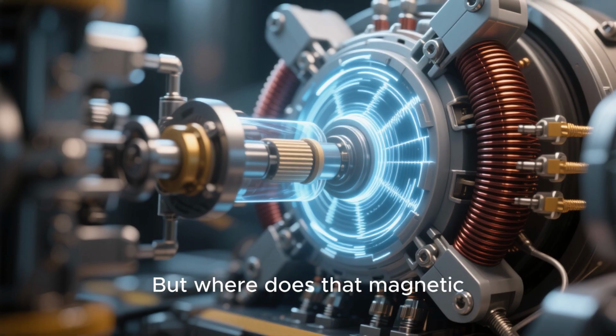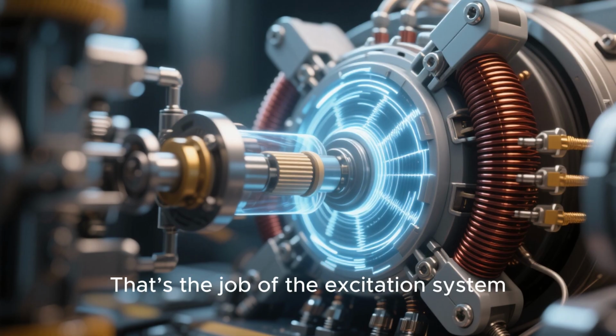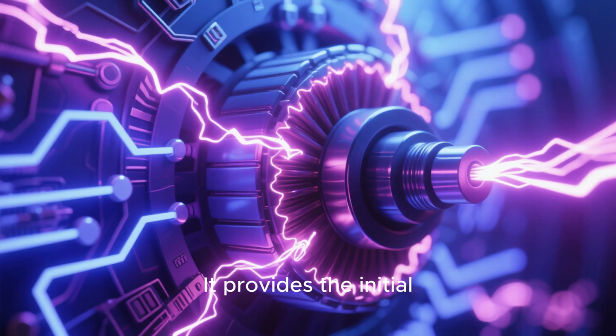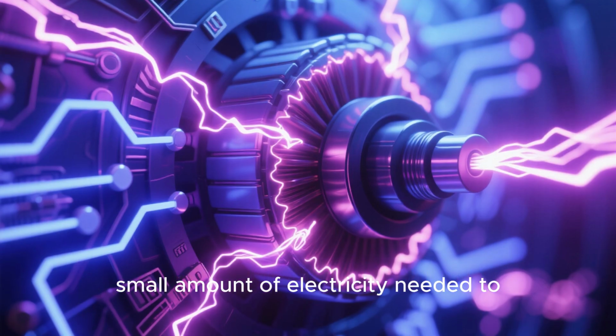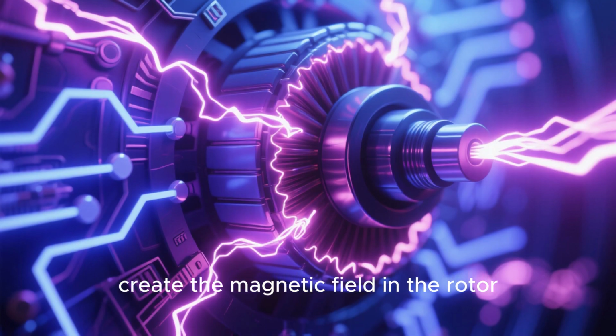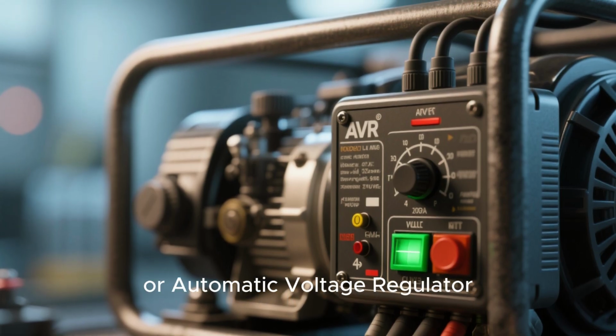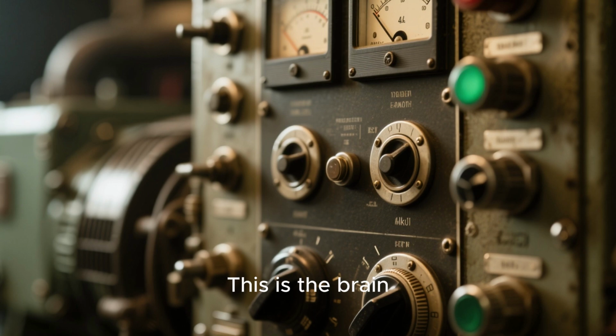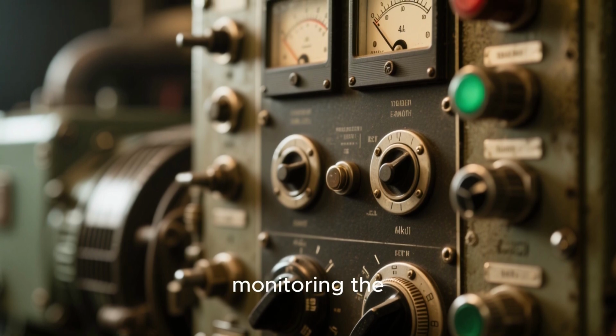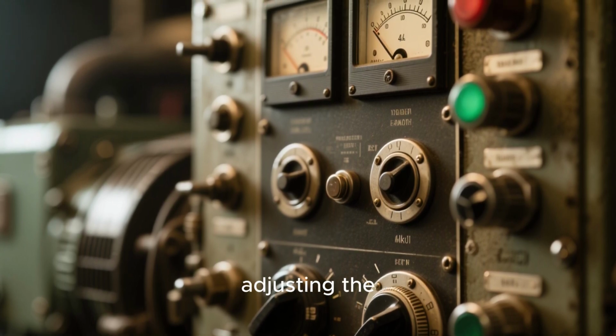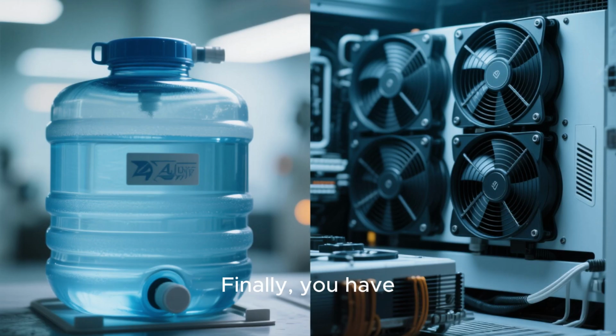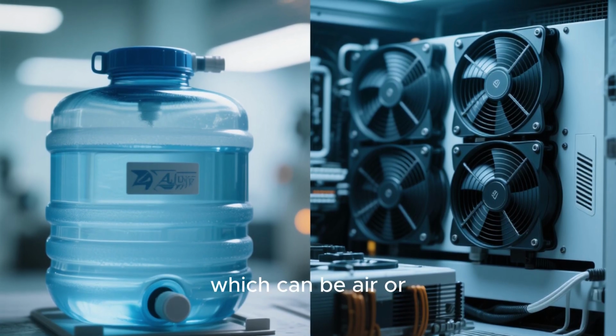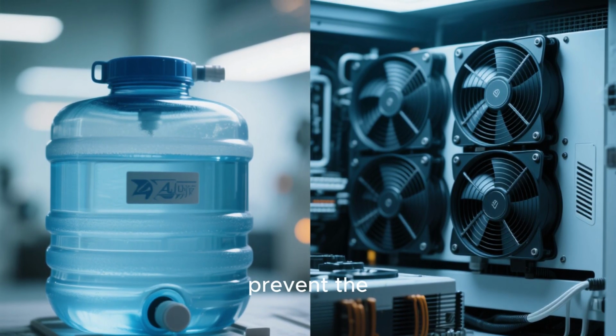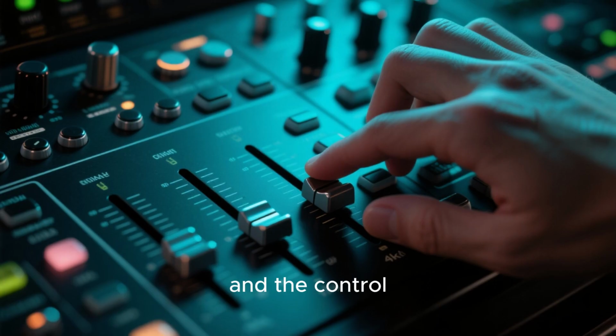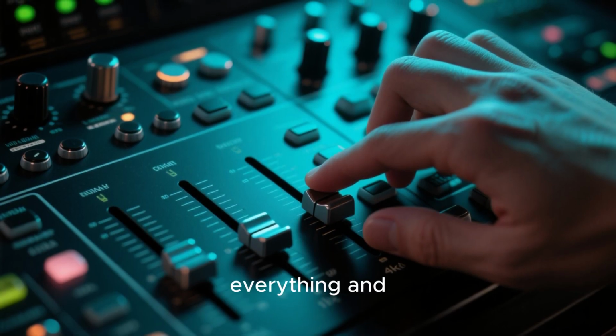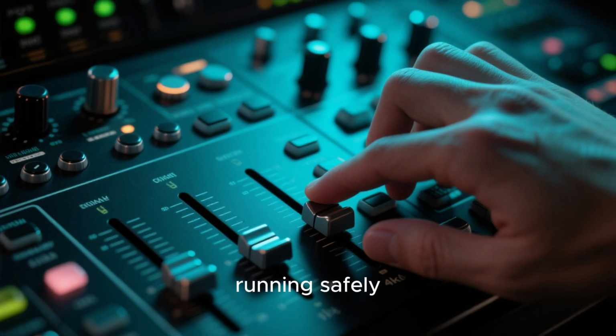But where does that magnetic field come from? That's the job of the excitation system. It provides the initial small amount of electricity needed to create the magnetic field in the rotor. Then there's the AVR, or automatic voltage regulator. This is the brain of the generator, constantly monitoring the output voltage and adjusting the excitation to keep it stable. Finally, you have the cooling system, which can be air or water-cooled, to prevent the generator from overheating, and the control panel, where you can monitor everything and ensure it's all running safely.